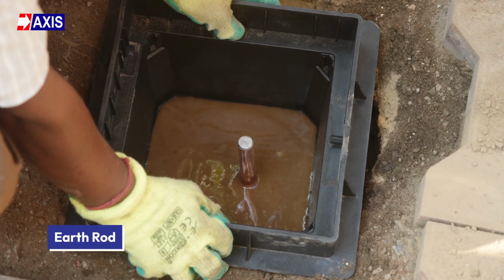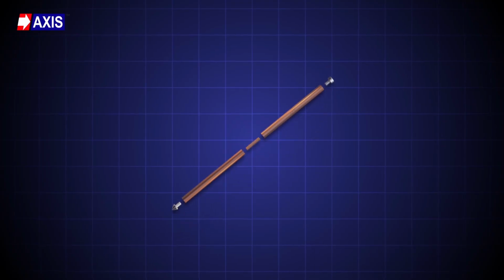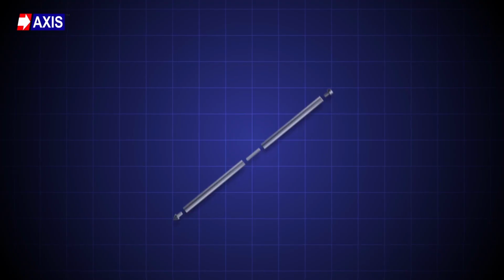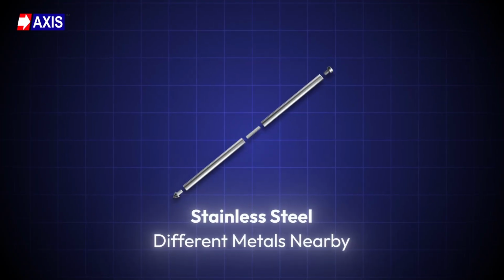Secondly, the earth rod. This is a metal conductor buried deep in the ground. It carries fault currents from your electrical system and dissipates it safely into the soil. However, the material you choose for your rod is crucial. In high corrosion areas, you need solid copper rods. In areas with different metals nearby, stainless steel rods prevent galvanic corrosion.